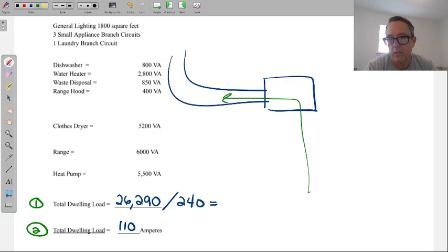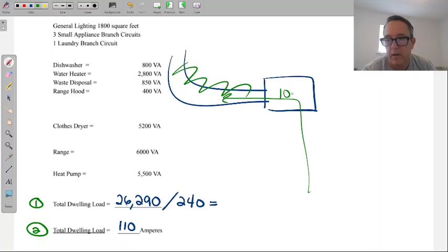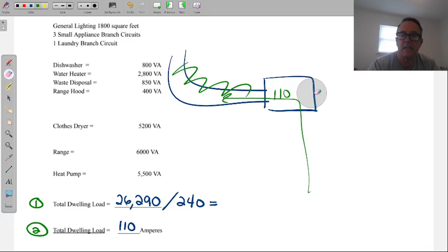The job of the main breaker is to make sure that as things get turned on, the wires coming to this main breaker, handling all the amperage from this house, are protected. If anything overloads, this breaker will trip. But this breaker is never dealing with an overload unless, in the future, the homeowner buys an EV system, a jacuzzi, or whatever else they want to install. Then this 110 needs to be resized.